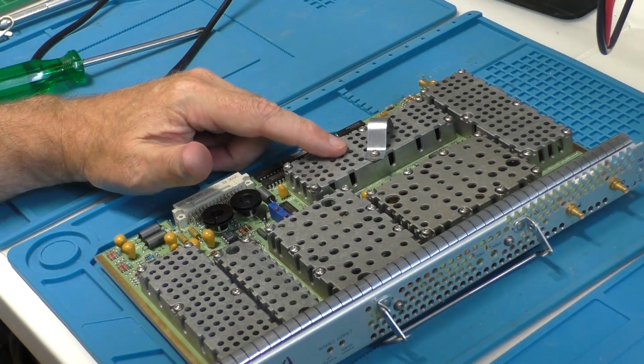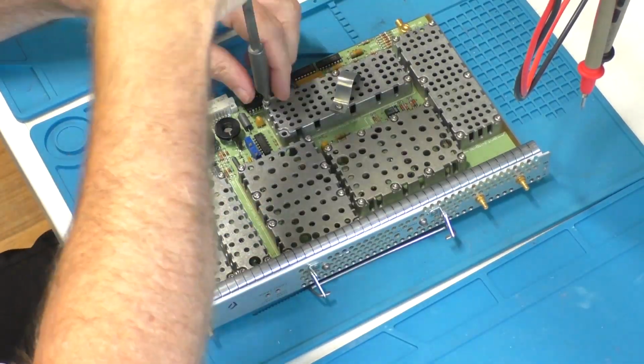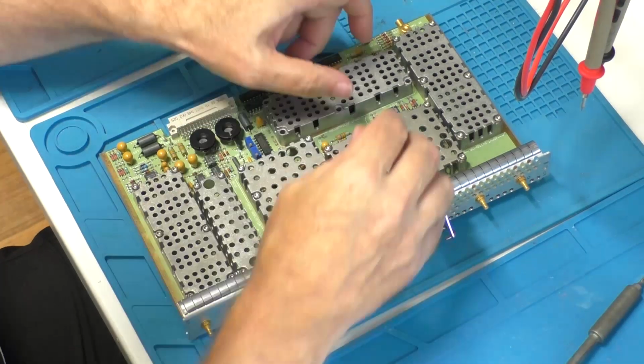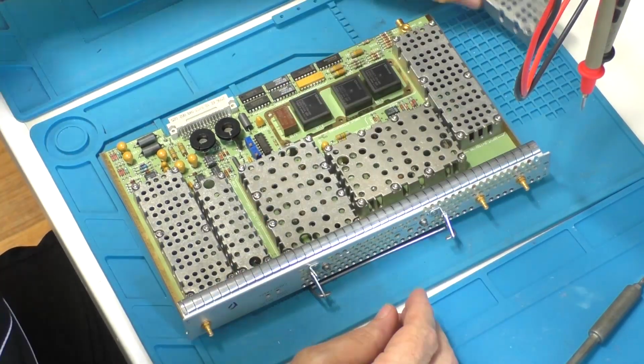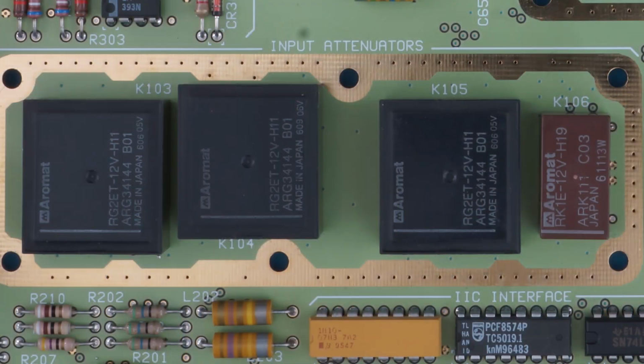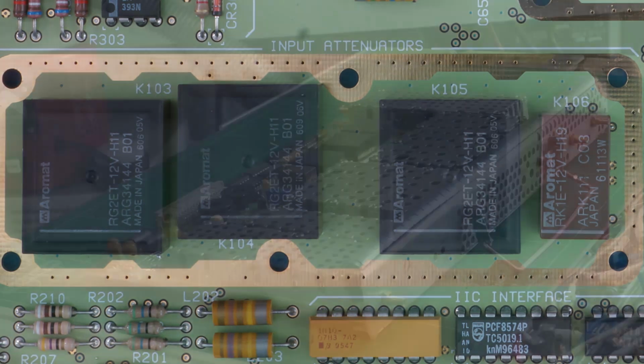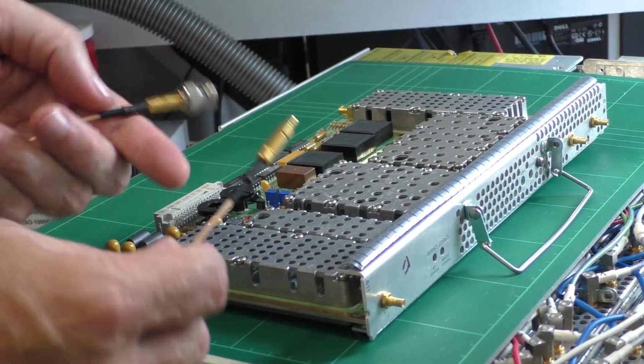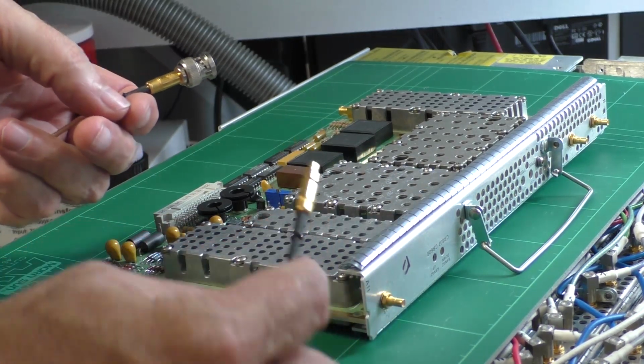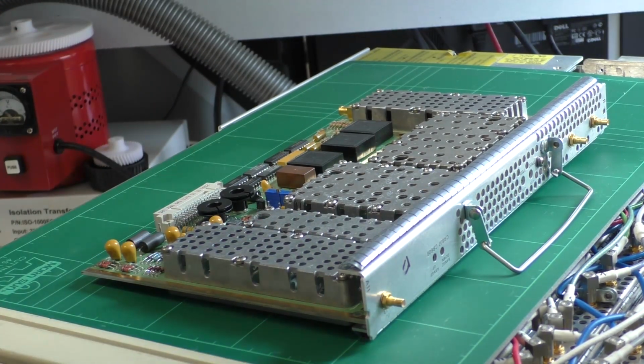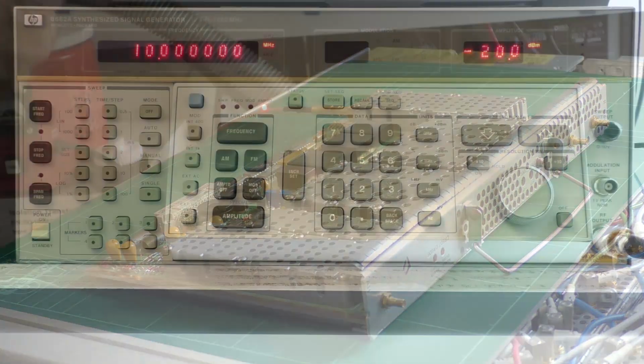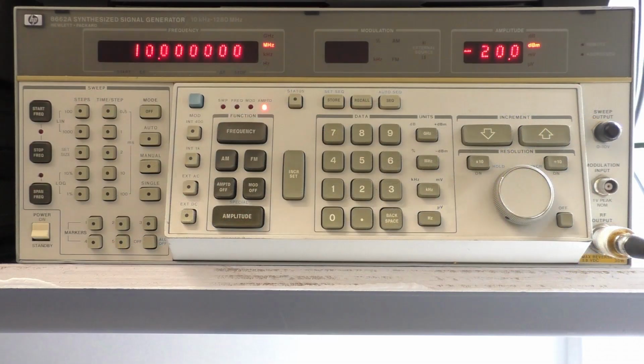Remove the shields from the input attenuators. Remove the 6 screws from the shields. Remove the shields and set aside. A close-up of the 3 attenuator relays. We will put the A11 into a riser and test in circuit. Place a patch cable on J4. This is the input connector. Connect the other end into our signal generator as used earlier.